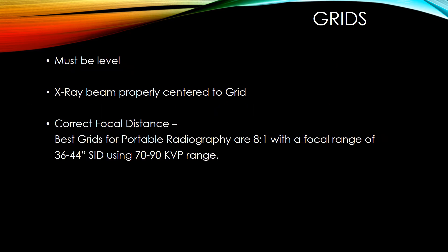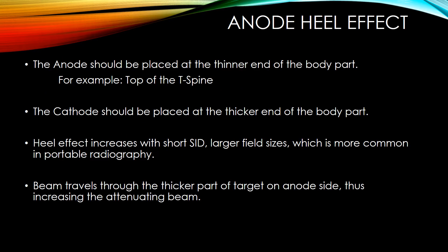Grids must be level, with the x-ray beam properly centered to the grid at the correct focal distance. The best grids for portable radiography are 8:1 with a focal range of 36 to 44 inch SID, using a 70 to 90 kVp range. Anode heel effect: the anode should be placed at the thinner end of the body part — for example, the top of the spine. The cathode should be placed at the thicker end. The heel effect increases with short SID and larger field sizes, which is more common in portable radiography.